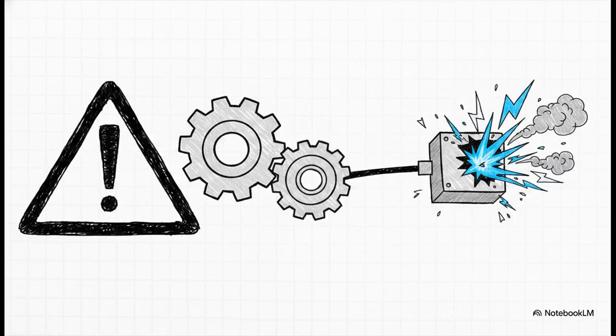But this physical mechanism is exactly why I have to deliver a pretty stark warning here. Never, ever apply high-impedance REF to mismatched CT ratios. Don't even try it just to see if it works, unless you really enjoy filling out extensive incident reports. If you mix a high-impedance scheme with severely mismatched equipment, say a 2,000 to 1 phase CT with a 1,000 to 1 neutral CT, that massive mismatch current during an external fault has nowhere to safely go but straight through the relay. You're risking false trips, or even worse, completely frying your protective components.